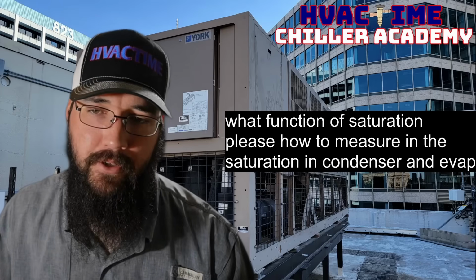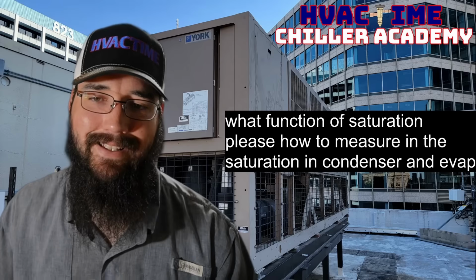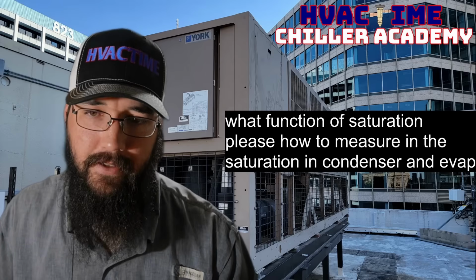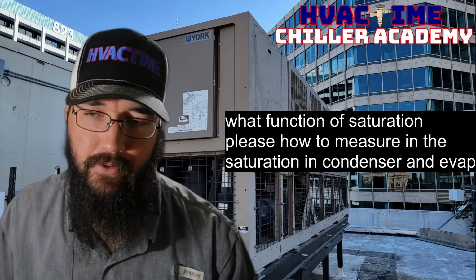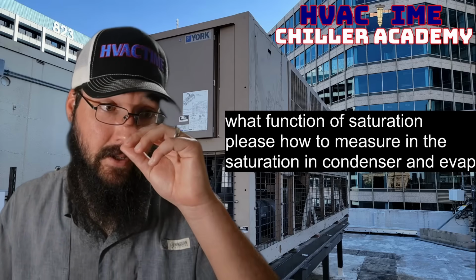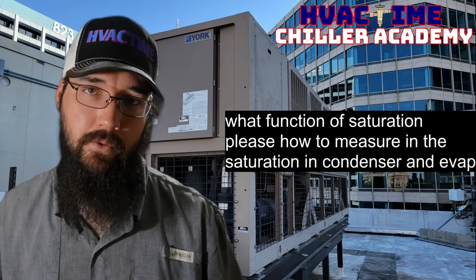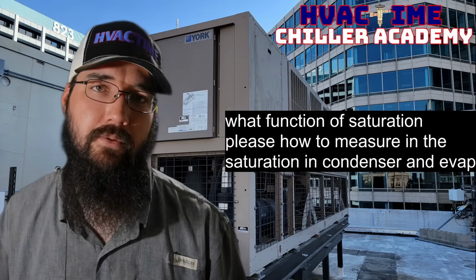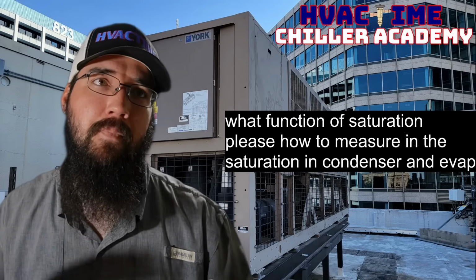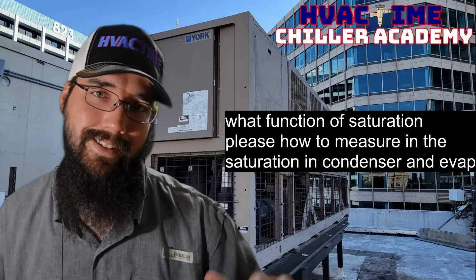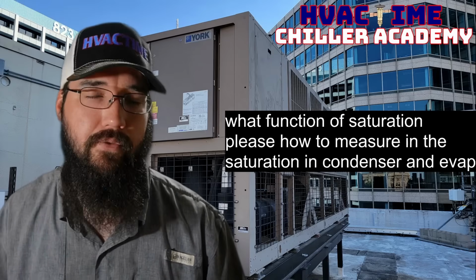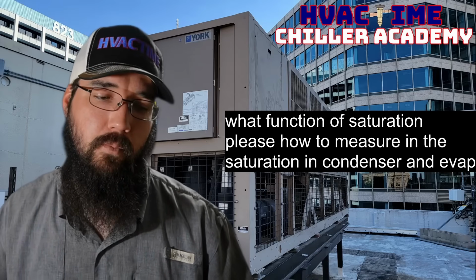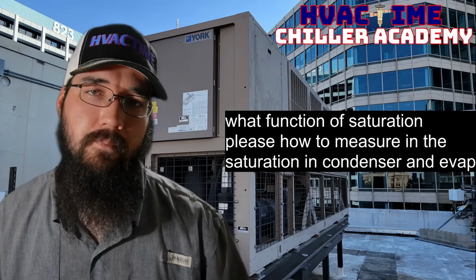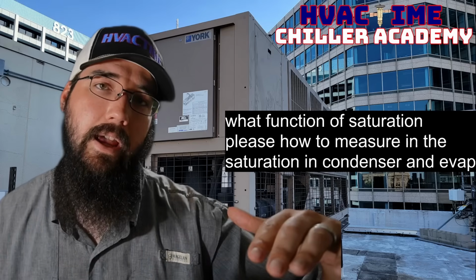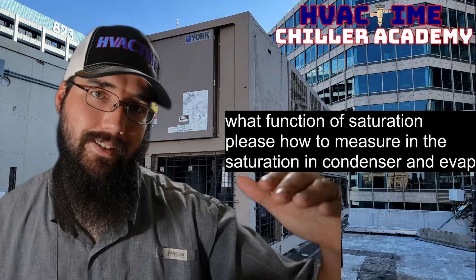What function of saturation, please, how to measure the saturation in the condenser and evaporator? So saturation, we're going to get into some basic principles here. Saturation is the boiling temperature or condensing temperature of a refrigerant. Just like with water, water will boil at 212 and then condense at 212.